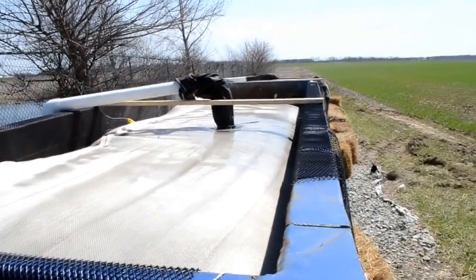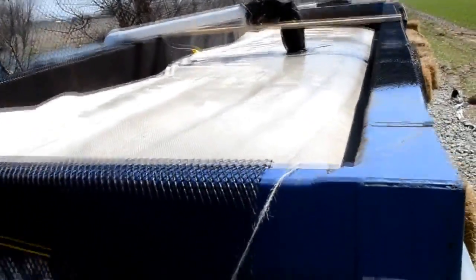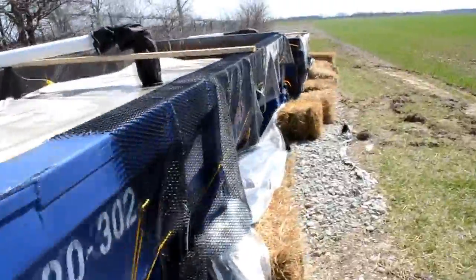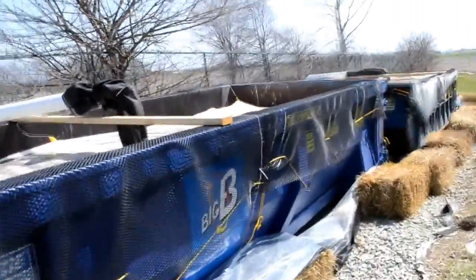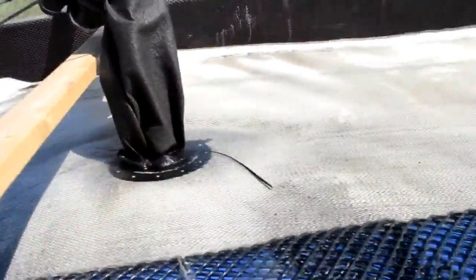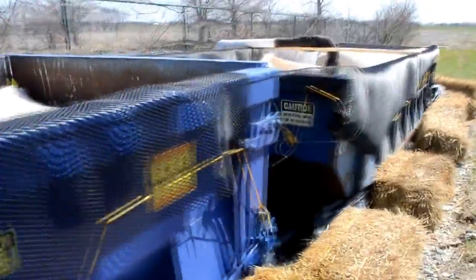The bag is 3/4 full of the slurry. With the container bag process, you pump the bag up to full capacity, allow it to dewater, and then pump it up again. 2 roll-offs are used to allow the operator to switch back and forth between the bags. In some cases, 6 or more roll-offs are used to keep the process rolling along.